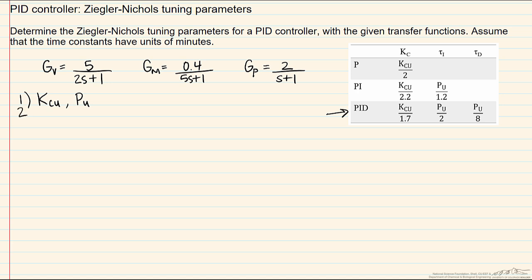In the continuous cycling method you are running your controller as only a P-only controller, and your goal is to get a response that is undamped. However, if transfer functions are known, if we can model the process, the valve, and the sensor transmitter with good accuracy...